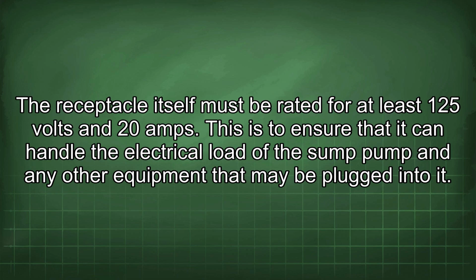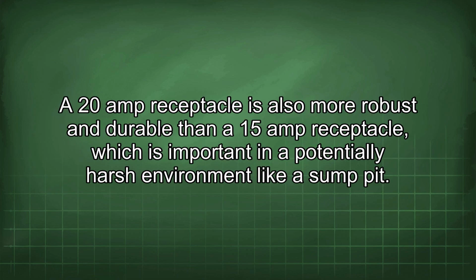This is to ensure that it can handle the electrical load of the sump pump and any other equipment that may be plugged into it. A 20-amp receptacle is also more robust and durable than a 15-amp receptacle, which is important in a potentially harsher environment like a sump pit.